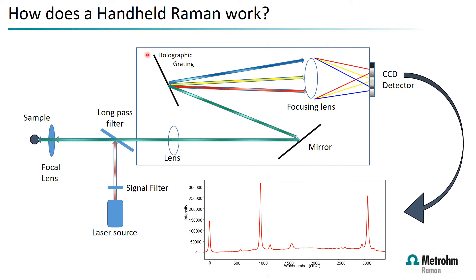We use free-space optics to send light through the system and split it on a holographic grating into its component wavelengths, then focus this onto a linear detector, which gives us the signal back into the device. There are no moving parts, so the light path does not require a moving mirror, making it completely insensitive to vibration and easily carried around.